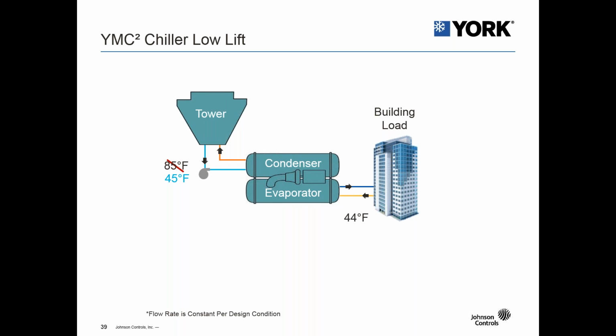Now with the YMC squared, we're able to utilize low tower water. So in this example, it's still able to run and provide the full building load at 45 degrees entering condenser water temperature. And on the evap side, it's still providing 44 degrees. So there's no reduction in the chilled water set point. There's no reduction in the flow on the condenser side. So it's not head pressure control. It's not variable flow on the evaporator side.